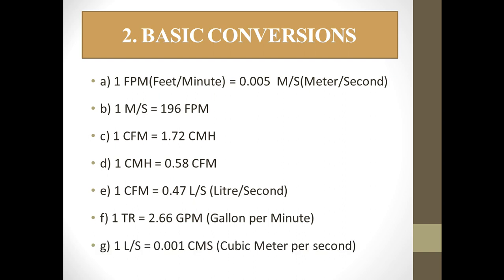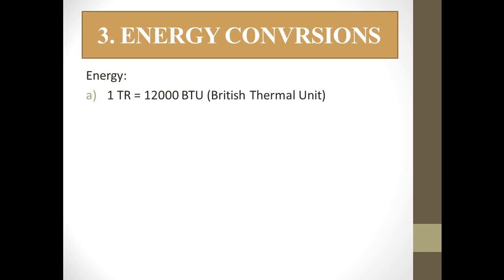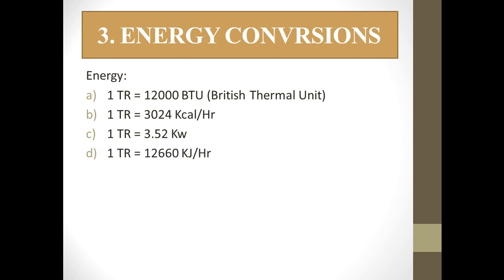(f) 1 TR = 2.66 GPM (gallons per minute) — applicable only in water-cooled chillers; (g) 1 liter per second = 0.001 cubic meters per second. Now let us come to energy conversions: (a) 1 TR = 12,000 BTU (British Thermal Units); (b) 1 TR = 3024 kcal per hour.